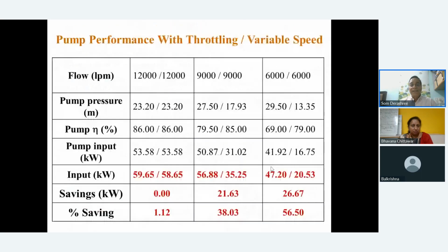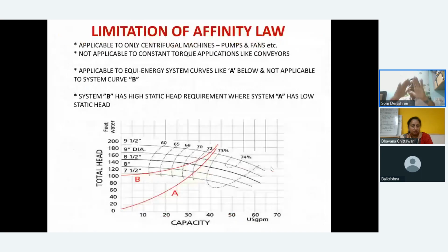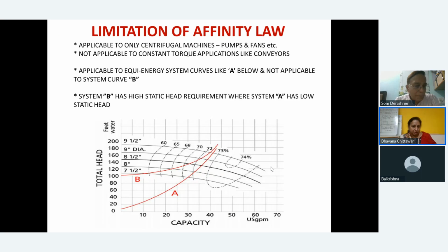If the system curve is like this, where the static requirement is almost flat, then putting a VFD, your pump will be rotating, but you will not have adequate water at the top. So that you have to take care of. Okay. Anything else? Yeah. Next question.